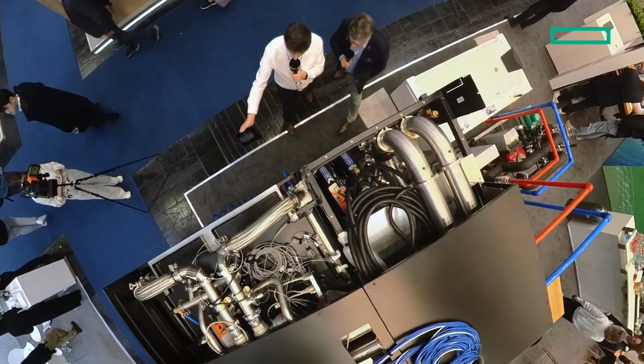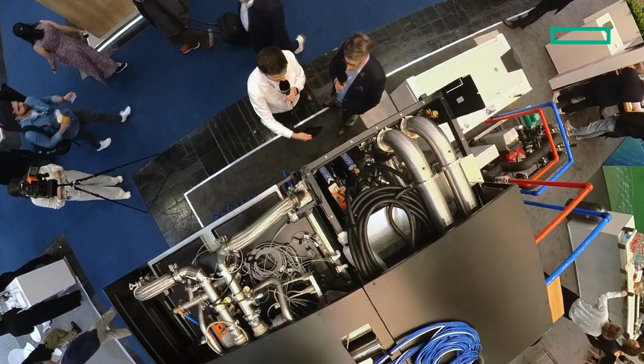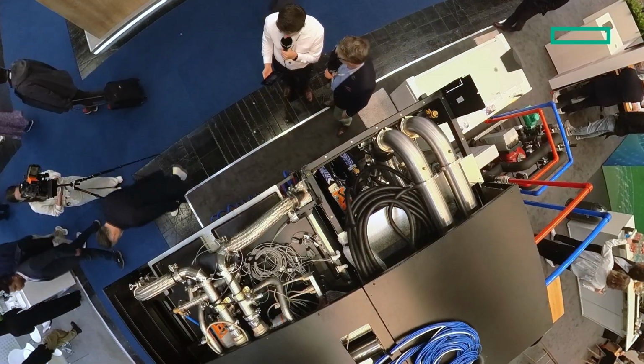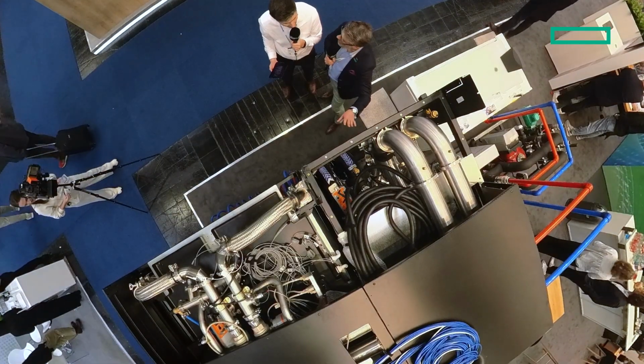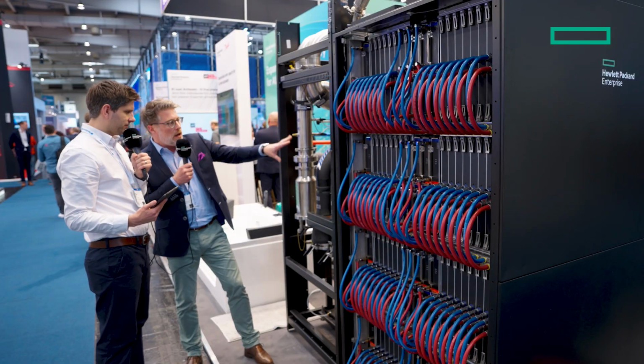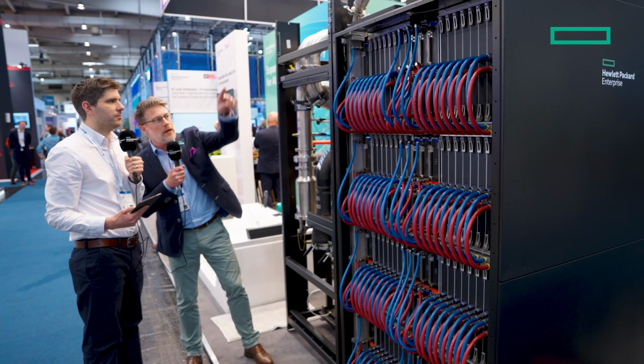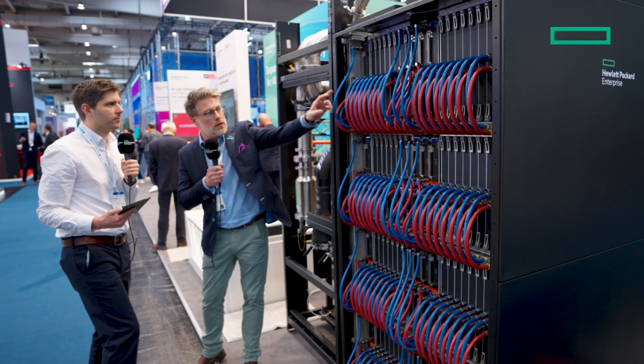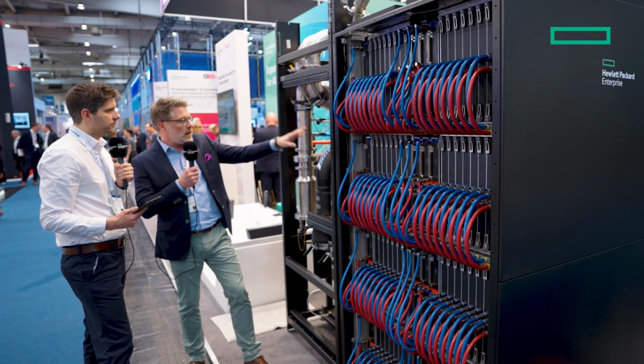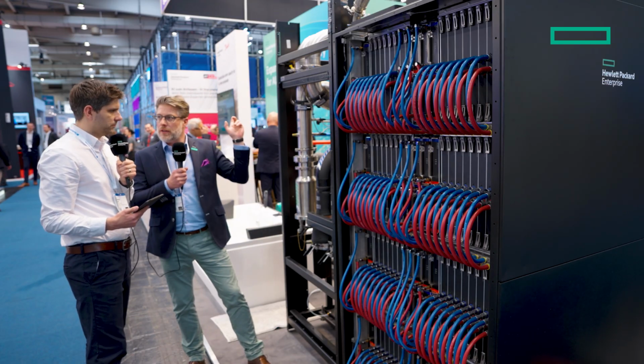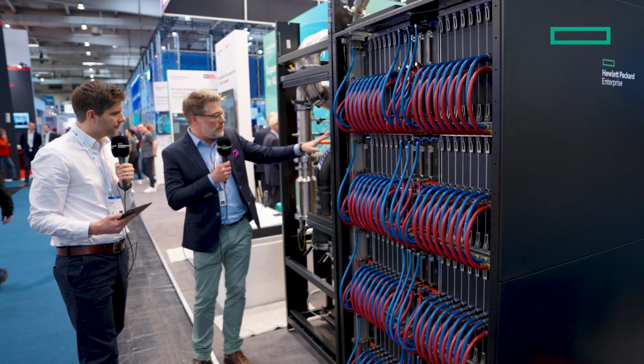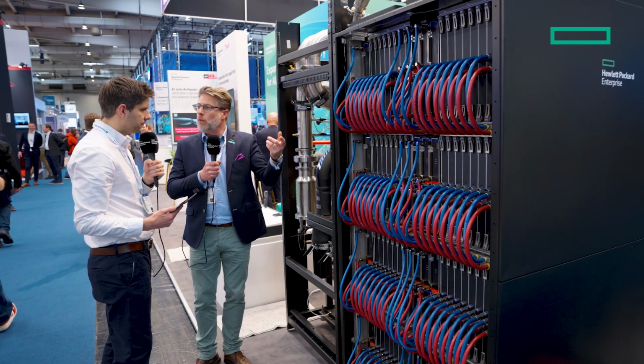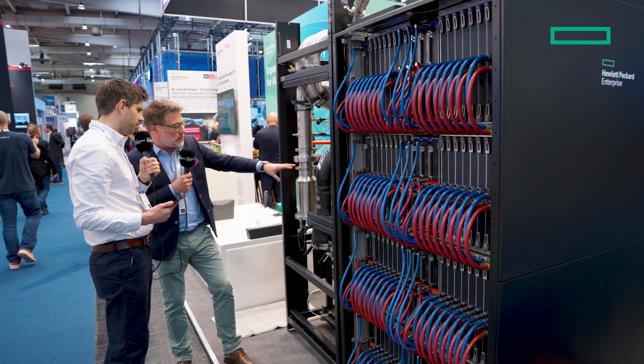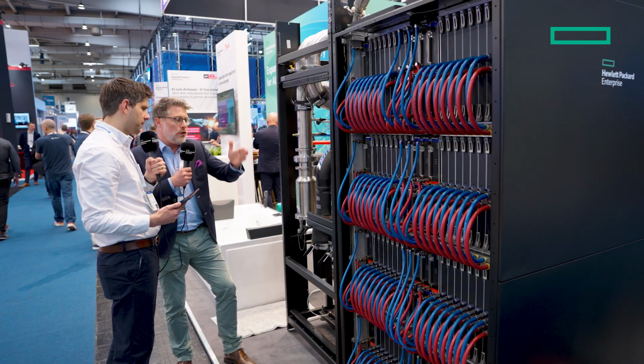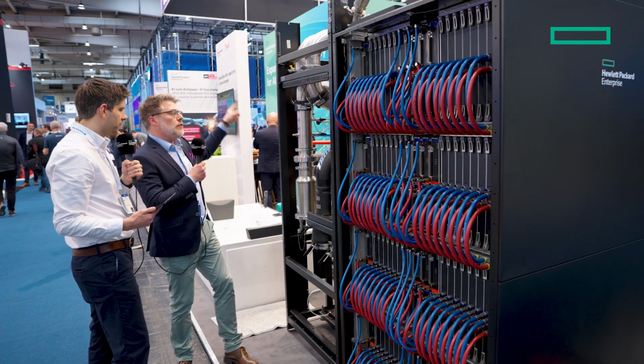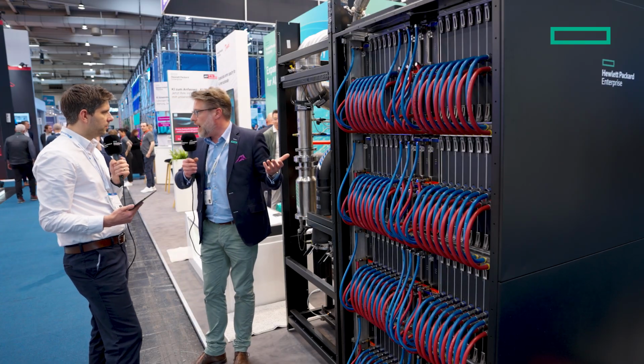So it looks like the water is coming in and out, hot and cold, into this thing - what's going on here? That is the CDU, a cooling distribution unit. So you have this one circulating the water cold into the blue ones and red warm out, and that can host 2 of those, left and right. And then you have pumps circulating the water, and here the possibility to transfer the heat out of that inner circle into another one, which you can use or have to use in the data center.